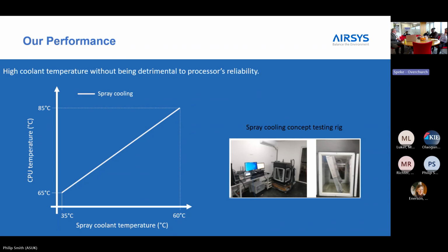And they're all very simple, really, in terms of it. The technology is the dielectric fluid being stable over a period of time, because it's about $25 a litre, and some of these installations have 500 or 1,000 litres of dielectric in them. So that's $25,000 before you start. So you don't want to be changing that every year. You want to be able to clean it and reuse it. So a lot of these manufacturers of the dielectric currently are testing the long-term efficacy of their particular product in the marketplace. So in about 3 to 4 years' time, I would suspect that will then be coming across the industry.